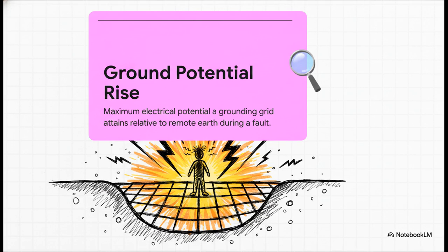Under normal conditions, the ground beneath a substation is sitting pretty at zero potential. But when a fault occurs, the system intentionally dumps thousands of amps of current into the earth to clear it from the wires. Now, because the soil naturally has resistance, dumping that much current causes an instant, deadly spike in voltage known as ground potential rise, or GPR. Essentially, the literal dirt you are standing on suddenly becomes electrically charged relative to the remote earth around it.